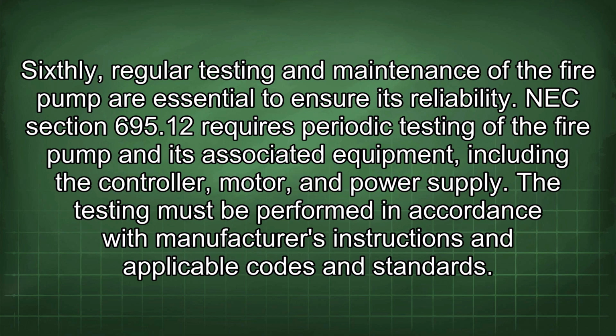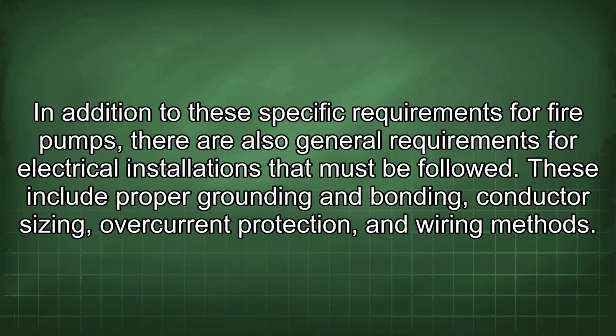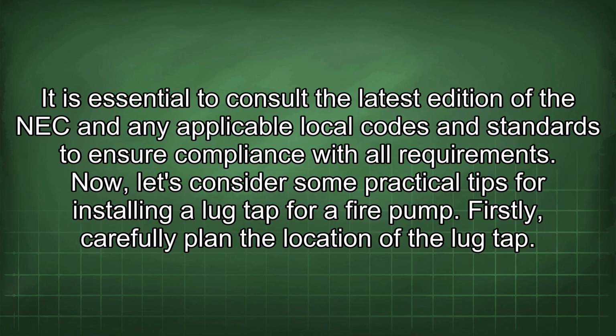Sixthly, regular testing and maintenance of the fire pump are essential to ensure its reliability. NEC Section 695.12 requires periodic testing of the fire pump and its associated equipment, including the controller, motor, and power supply. The testing must be performed in accordance with manufacturer's instructions and applicable codes and standards. In addition to these specific requirements for fire pumps, there are also general requirements for electrical installations that must be followed. These include proper grounding and bonding, conductor sizing, overcurrent protection, and wiring methods. It is essential to consult the latest edition of the NEC and any applicable local codes and standards to ensure compliance with all requirements. Now let's consider some practical tips for installing a lug tap for a fire pump.